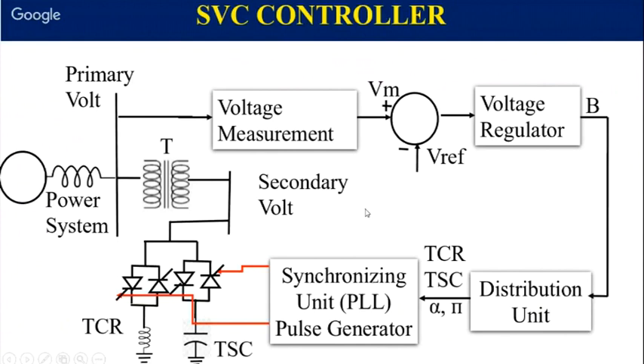So it is very simple. Voltage measurement is done. It is compared with the reference. How much voltage is to be supplied by the SVC is calculated. How much the susceptance should be to provide that voltage is calculated. Which banks should be on and off is decided. And how much the delay angle for the reactor should be is calculated. Because when you switch on a capacitor bank, though the requirement is less, whatever the capacitor bank is providing will be generated. But the surplus capacitive reactive power is cancelled by the reactor.